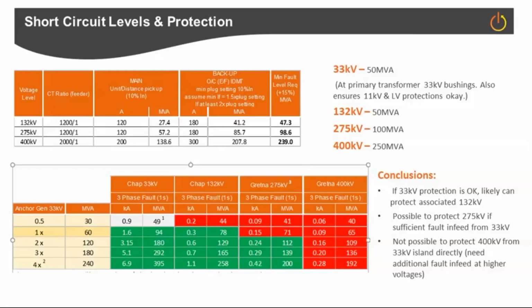So the conclusions basically lead us to think that, yes, we can utilize the bottom-up approach from 33 up to 132 kV networks and have the protection systems that were in place before the blackout should function. But once you start going up to transmission level, you'll need either to increase the short circuit levels by integrating more generation into that power island, or have some way of reducing the protection settings. Now, I know modern protection schemes have a weak network capability, and some of them can be remotely instructed from the distribution network control centers. So that's again a key finding for us. It does complicate our overall solution, but a key finding.